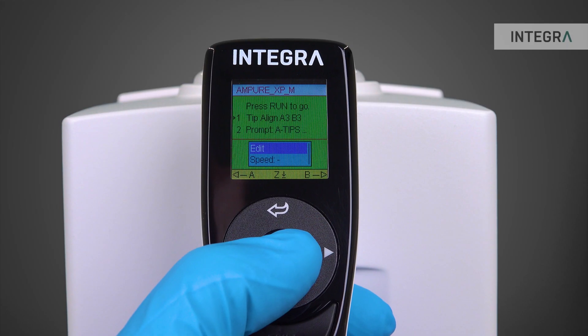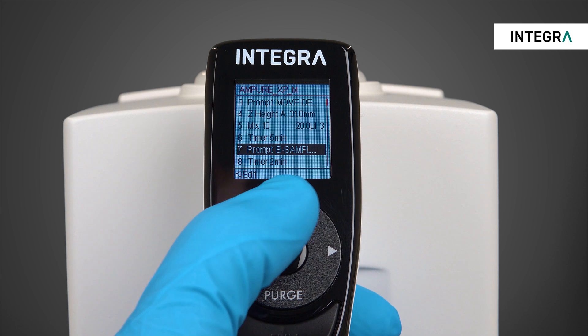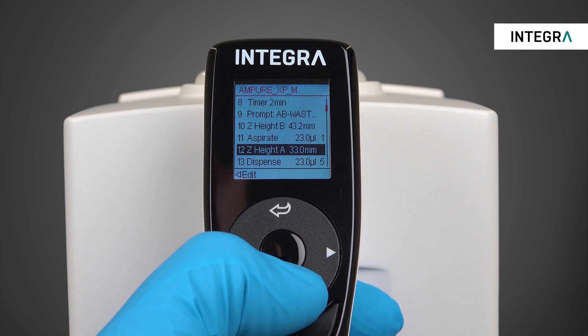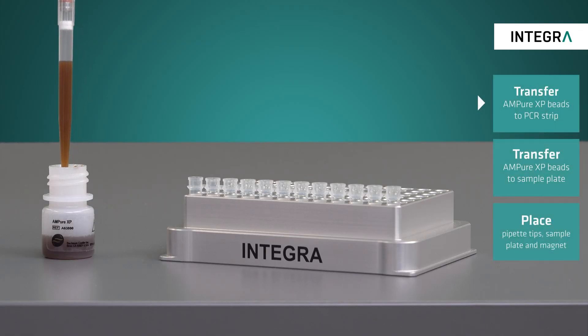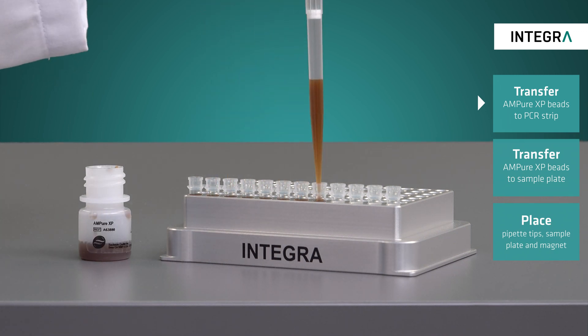The steps needed to run this procedure are saved as one single custom program called AMPure XP M on the VIAFLOW 96. It contains all the necessary volumes, prompts and heights. To start, the magnetic beads need to be transferred into 12 PCR tubes using a single channel 1250µL VIAFLOW electronic pipette and a repeat dispense program, adding 154µL per tube.